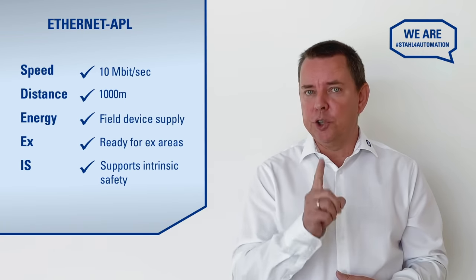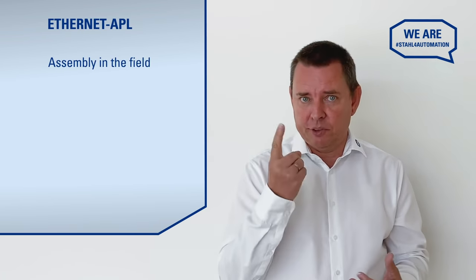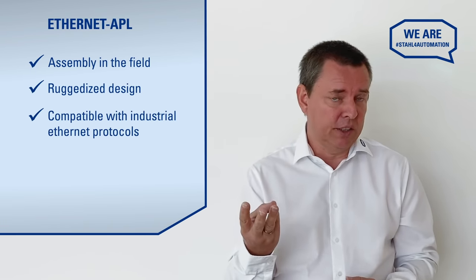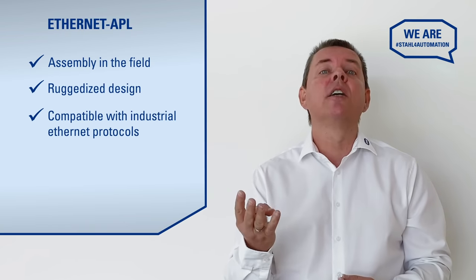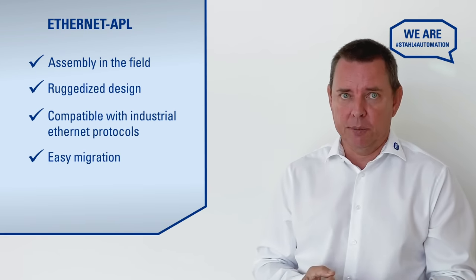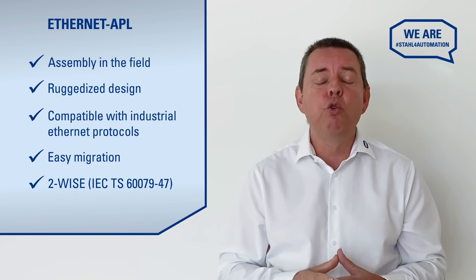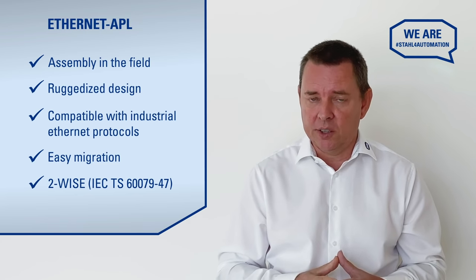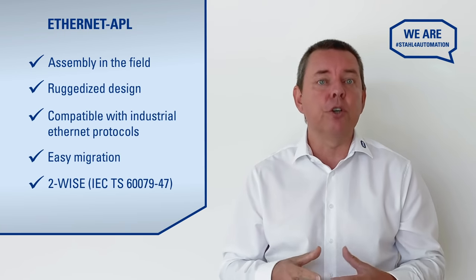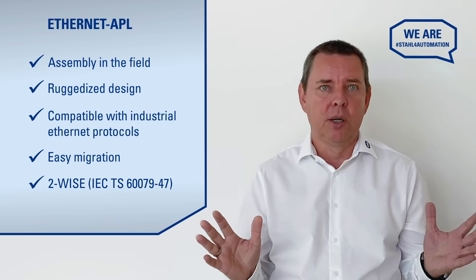What does all that mean for you? Ethernet APL can be installed in the field, it's rugged enough for heavy duty use, it's compatible with the relevant Ethernet protocols, and it offers a simple migration path because it uses familiar fieldbus type A cables. And maybe the best part — because it supports two-wire intrinsically safe Ethernet, it's easier than ever to verify the intrinsic safety of your loops, because two-wire approved devices don't require any calculations. Pretty neat, right?